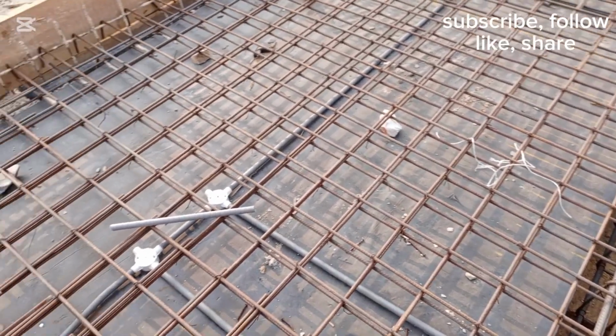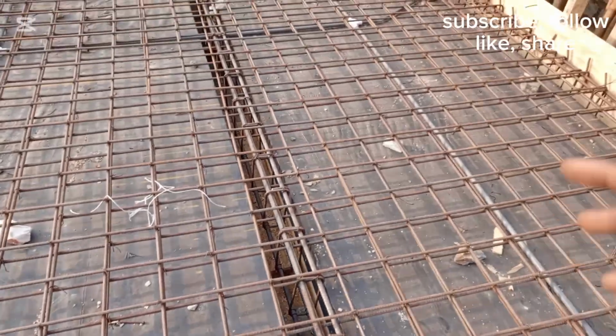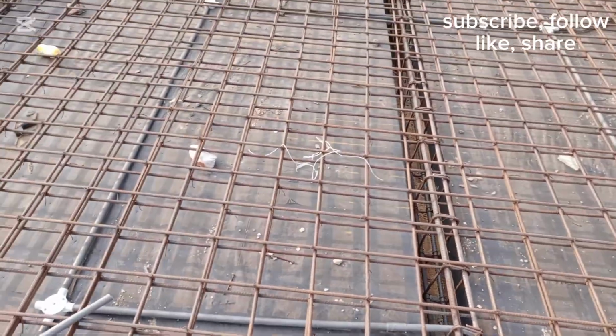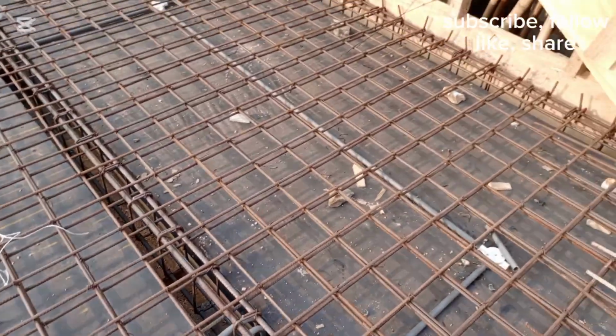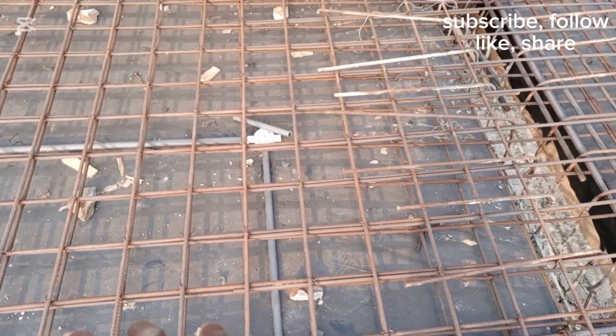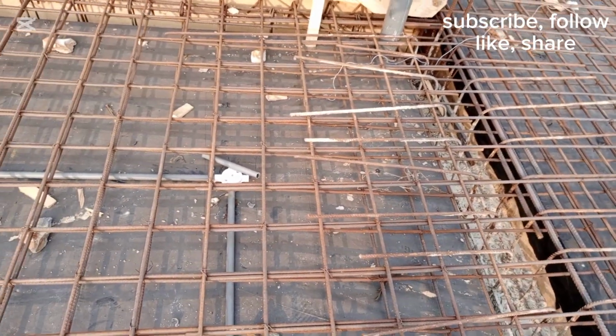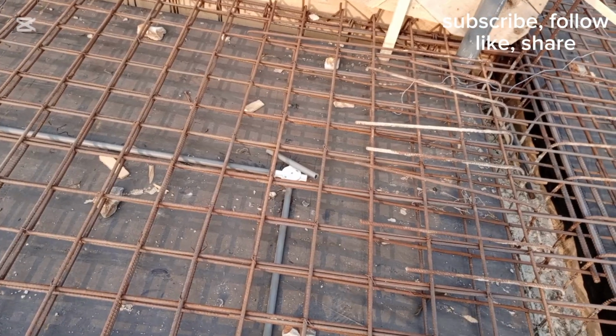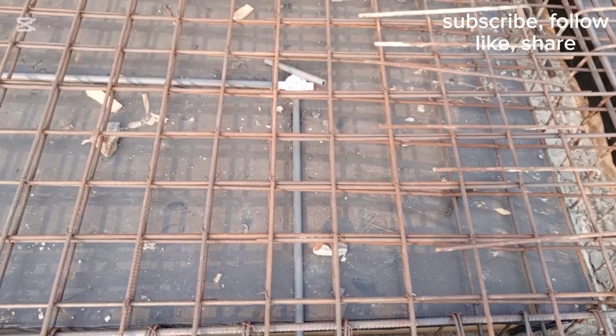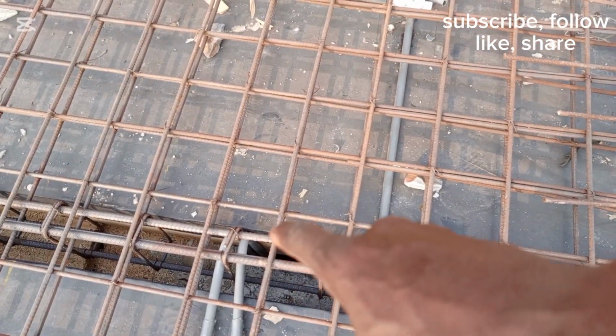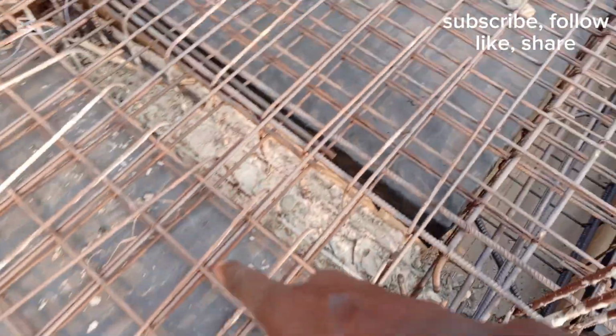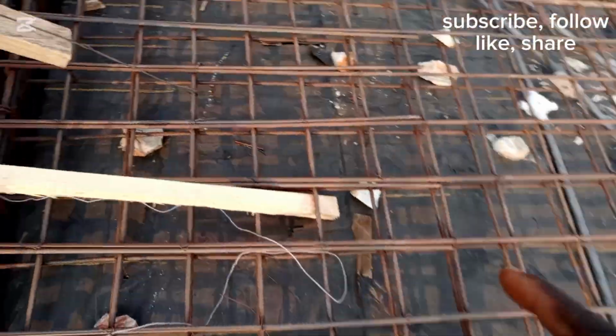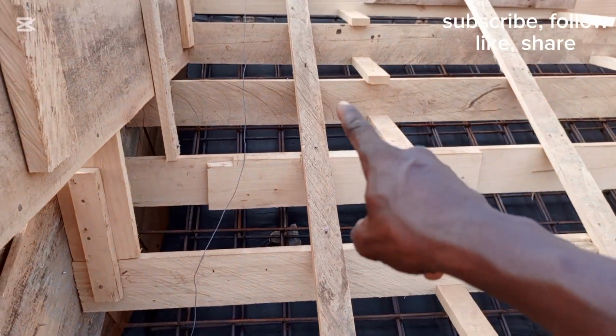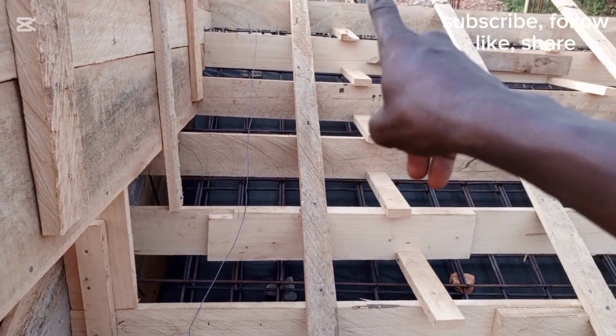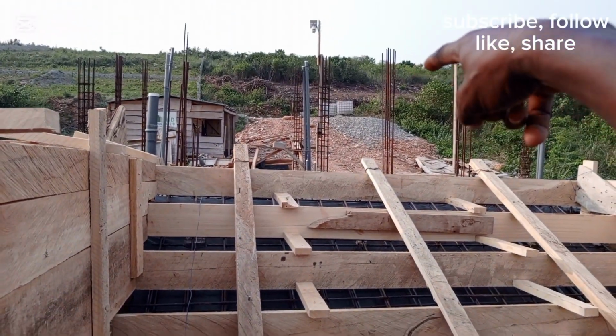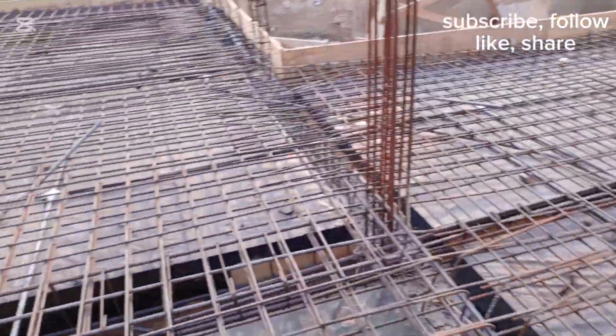for the swimming pool. Okay, so the thing is we need some kind of circuits here. So we're going to arrange 5 pipes. We are doing it 3-phase, and then an earth conductor. So that's 5 PVC pipes going through here. We will come through here, then it will climb this step up or down, and then it will go up there where the distribution board is.